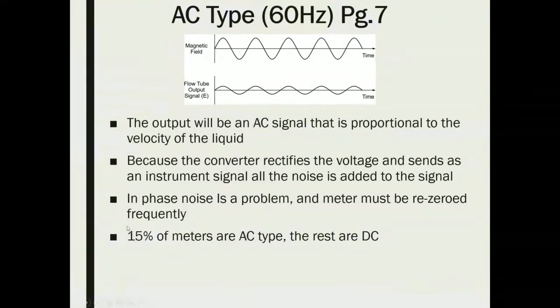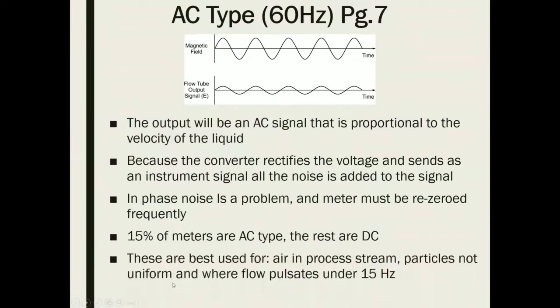About 15% of all mag meters out there are AC type; the rest are DC type. AC meters are best used for air in a process stream, applications where the particles are not uniform, and where we have flow pulsations under 15 Hz.